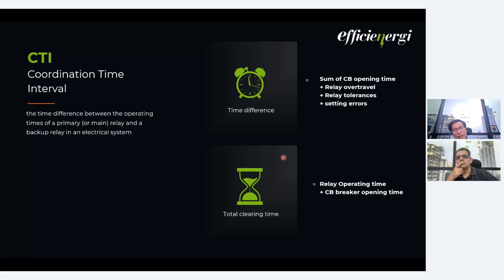So normally, what we see today is that there is very little margin that we get, and the system comprises many sub-levels. Up to the utility breaker, we have 3 to 4 stages in between, and we have to coordinate all these 3-4 stages. So considering 200 milliseconds for one stage, it comes to around 800 milliseconds or almost 1,000 milliseconds, which is impossible to coordinate with the utility breakers.